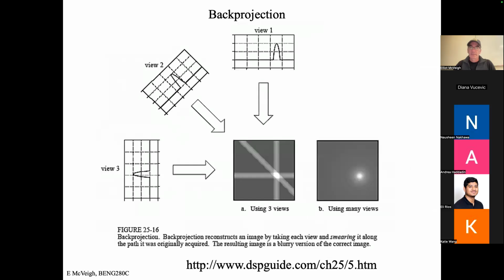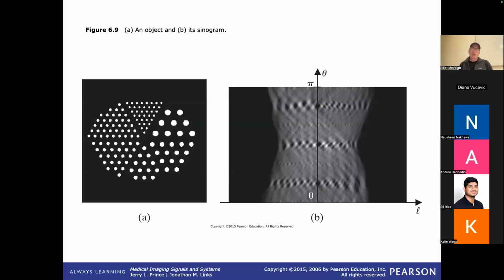Okay, we did this. So here's a more complex looking phantom. Granted, it's again a set of disks in a geometric pattern, but the projection through this as a function of angle is more complex than what we saw with the last single circle. So this is called a sinogram, and our detector position is along here. Remember, we had about 1,000 detectors along that direction on a CT scanner. So we can divide this up into about 1,000 measurements this way, on that order.